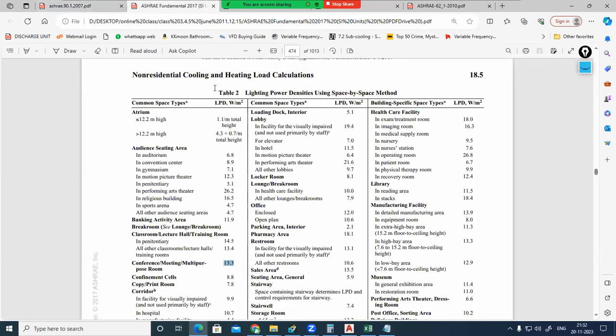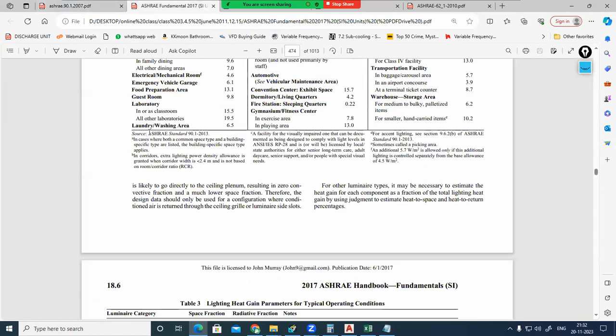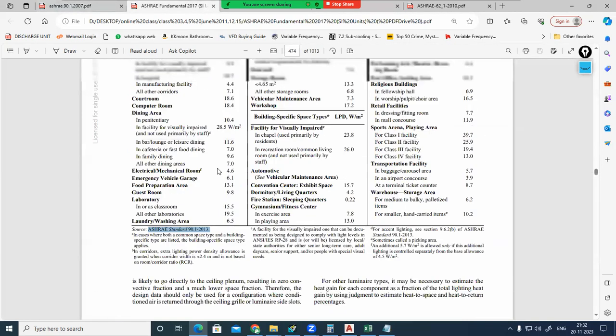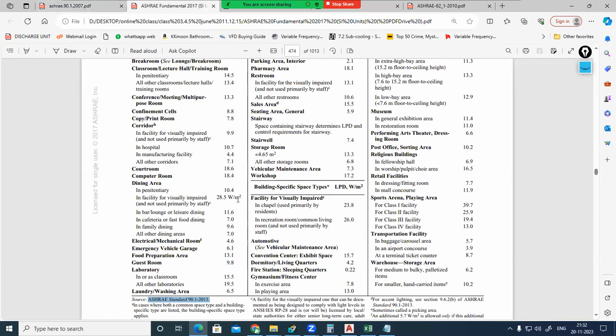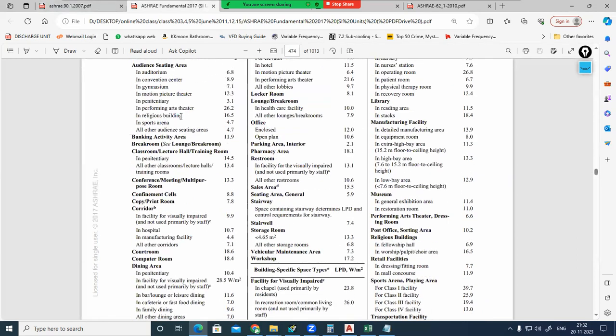A slight difference will be there between ASHRAE 90.1 and ASHRAE Fundamentals. ASHRAE Fundamentals also takes the data from where? ASHRAE 90.1 only. So they have considered this value as a reference from the ASHRAE 90.1 standard only. So you can take this LPD value. If you do not have the light fitting details, you can go for the ASHRAE 90.1 standard, any version, or the ASHRAE Fundamentals non-residential heating and cooling load calculation chapter. Okay, clear?